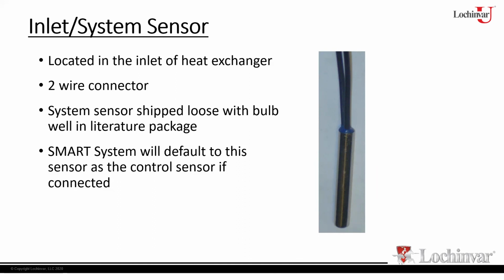You disconnect one sensor or one sensor fails, it's going to lock out on that particular sensor, right? It's going to say inlet sensor shorted or grounded. Same thing for the outlet sensor, it'll say the same thing. So again, make sure that the sensors are connected. There is a sensor shipped loose, which would be used as a system sensor or a tank sensor if it was a water heater. I do recommend using those sensors instead of just relying on the sensors inside the heat exchanger.